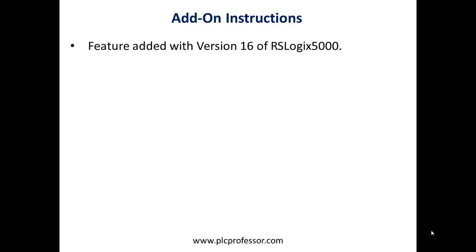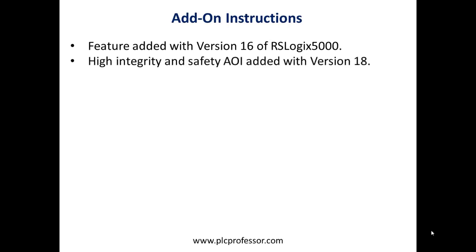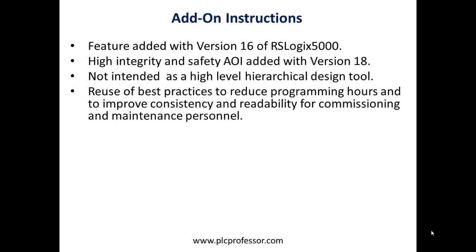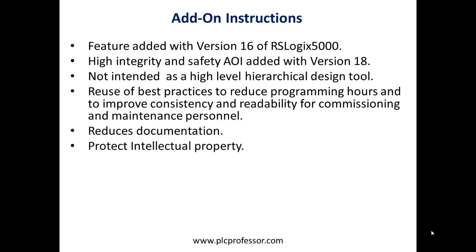Another class of add-on instructions called high integrity or safety were introduced with version 18. Add-on instructions were not meant to be used in the same manner as multiple routines, programs, and tasks — they're not meant to organize your logic. Once you discover an excellent thread of code that you use over and over again, you can create a template to reuse it without totally re-declaring each variable for each reuse. Not only does this improve consistency, but it simplifies readability for both commissioning and maintenance personnel. You can also hide your logic from competitors, thereby protecting your intellectual property.